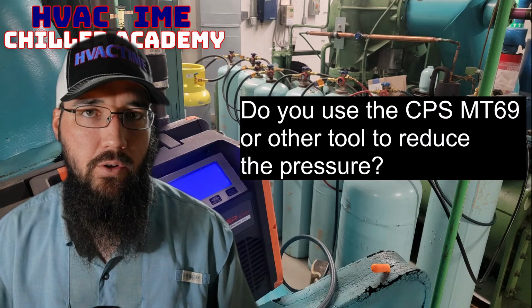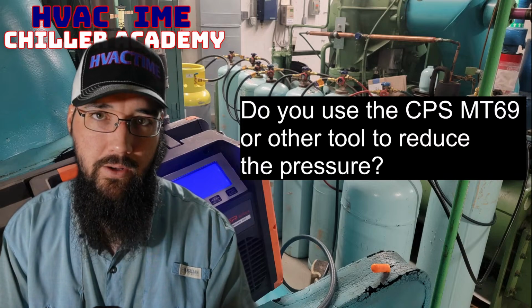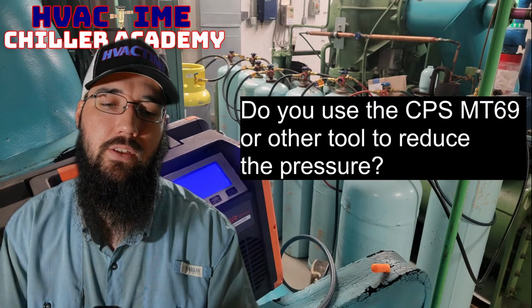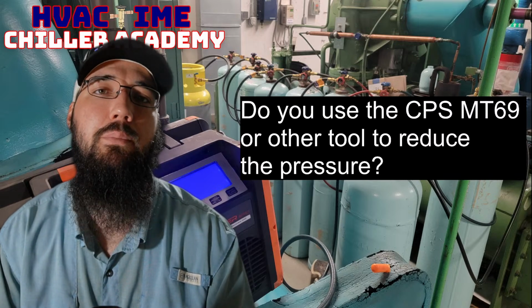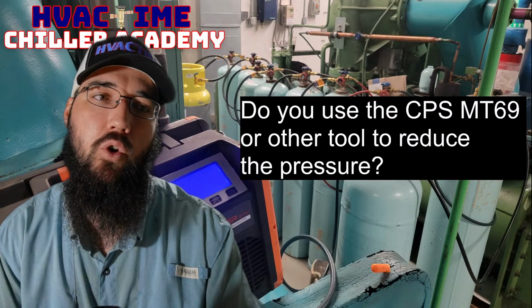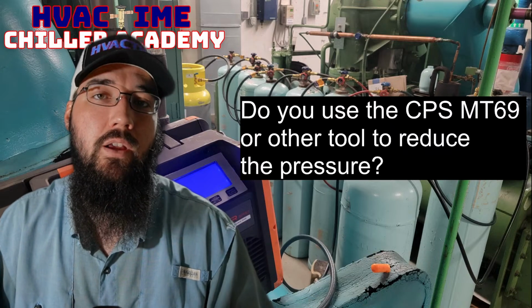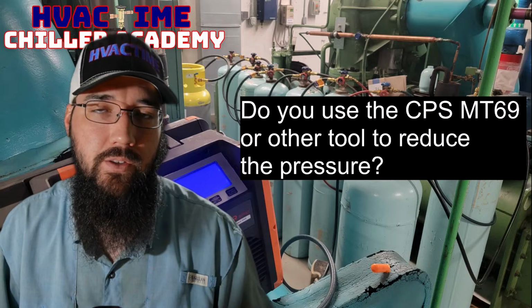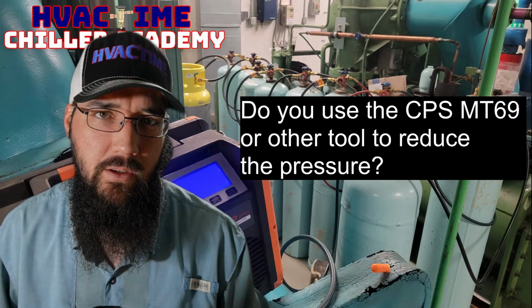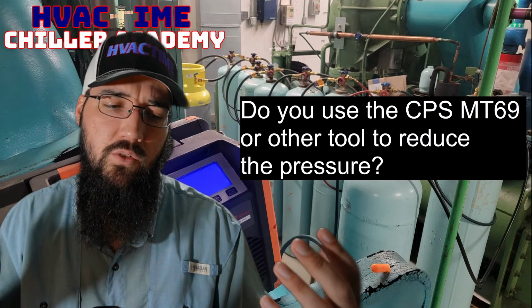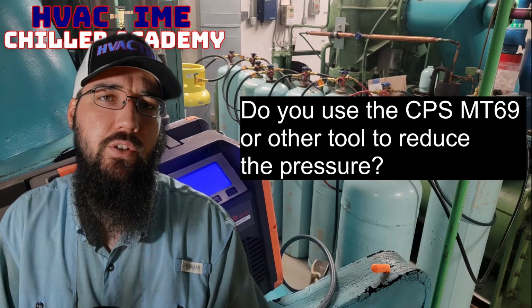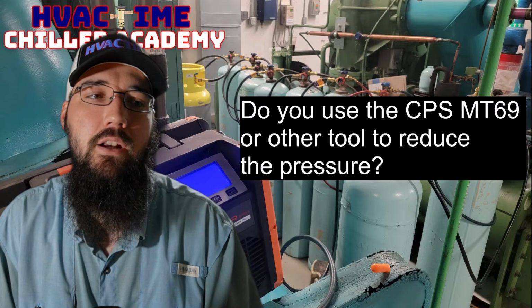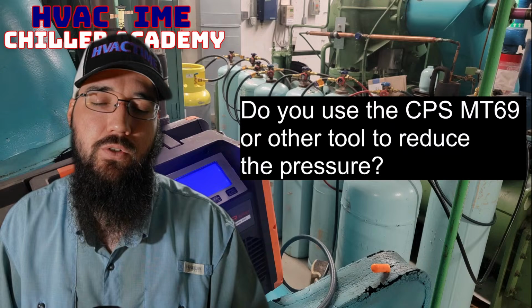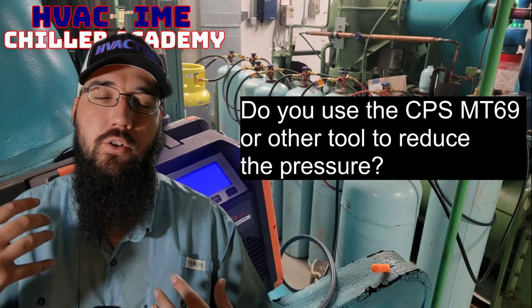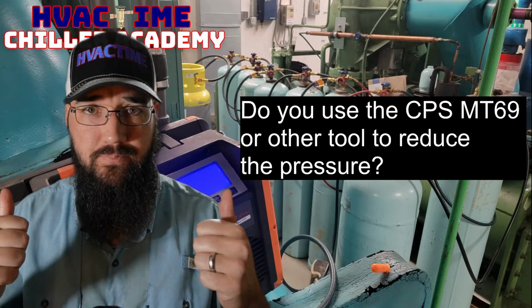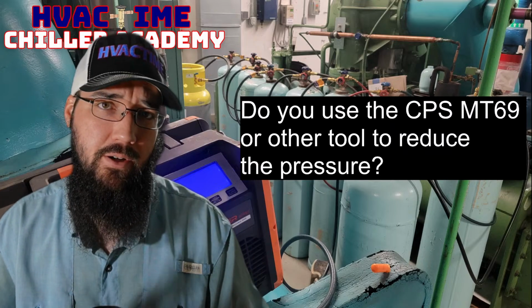And if all you're doing is smaller equipment, that little CPS one is great for that. My issue is it struggles to keep up with high volumes over an extended period of time, which is what we're doing when we're doing a chiller recovery. Like, we're moving hundreds of pounds, and this would be in an air-cooled application specifically. So even if you're trying to use this on a larger water-cooled, it's not big enough. It's not adequate for that type of application. So that's where, in my opinion, creating your own out of just a copper coil is probably better. You get better operation out of it.